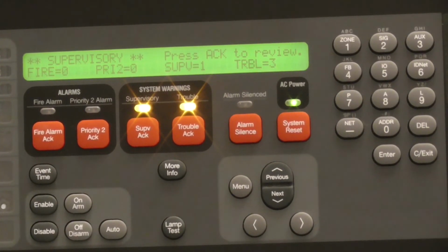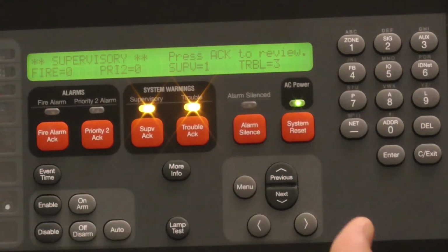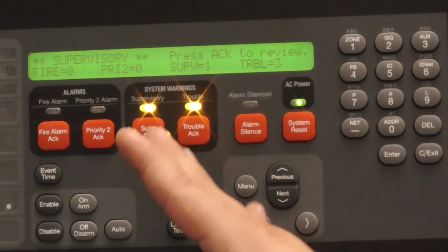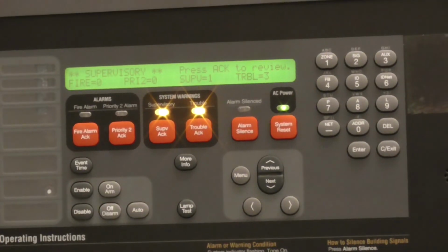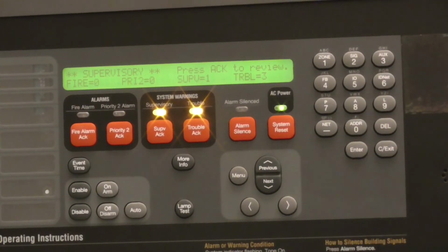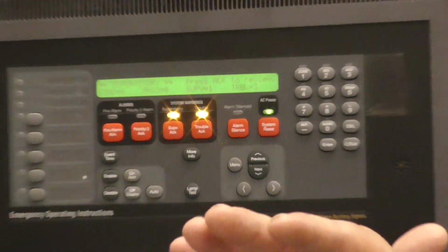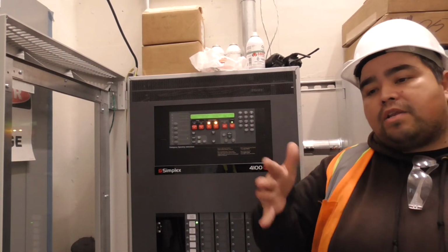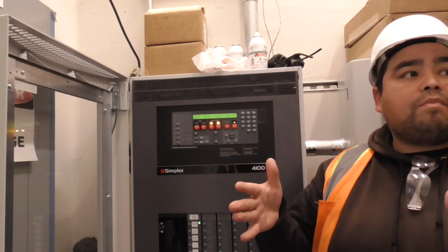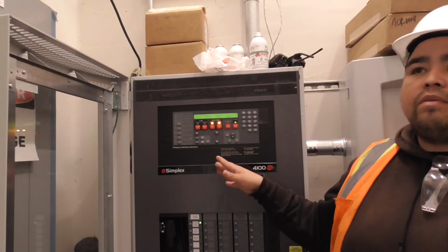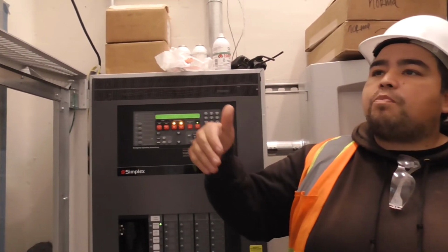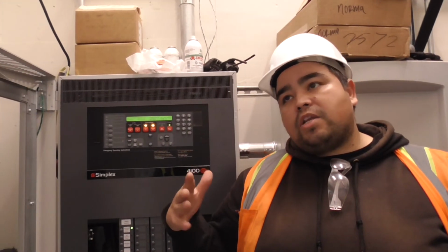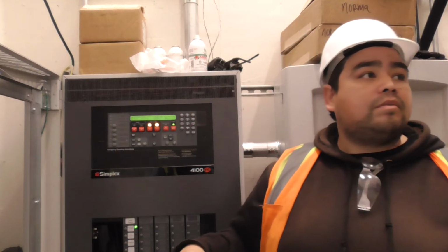You can, but what happens is it starts becoming a limitation of the panel if you don't have a specific NDU. I don't remember the exact number, but I think you could only bring 2,000 externals into one of these panels from another panel. So you could, up to a certain point where it's maxed out, and then you'd have to put an NDU in anyways. So really the right way to do it is have an NDU that only serves that purpose instead of using the building panel. It's a lot fewer points going over the network when I'm just sending the event itself. If it was an NDU, I would just send everything over there.